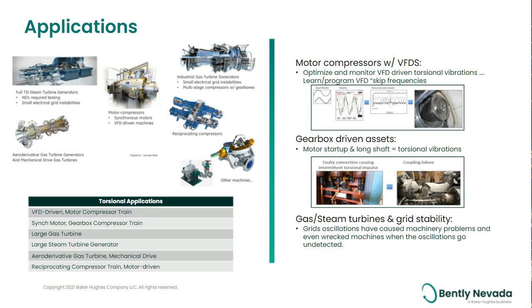As technology advances, the use of variable frequency drives certainly increases the efficiency of these motors and the output that can result. However, variable frequency drives, by their very nature, they are digital. They're looking to vary, again, the frequency coming through, and they do this in basically a step fashion. Very small to see, I understand, but if you can look at that image on the left, in a perfect world, it would be a sinusoidal wave, if you will, nice and smooth as that variable frequency drive is functioning. In reality, the programming looks to mimic that nice smooth wave, but it does it digitally with small incremental step changes. These are the step changes that can cause and can excite some minute torsional resonances or torsional vibrations, which unfortunately can result in catastrophic failure or damage to a shaft.